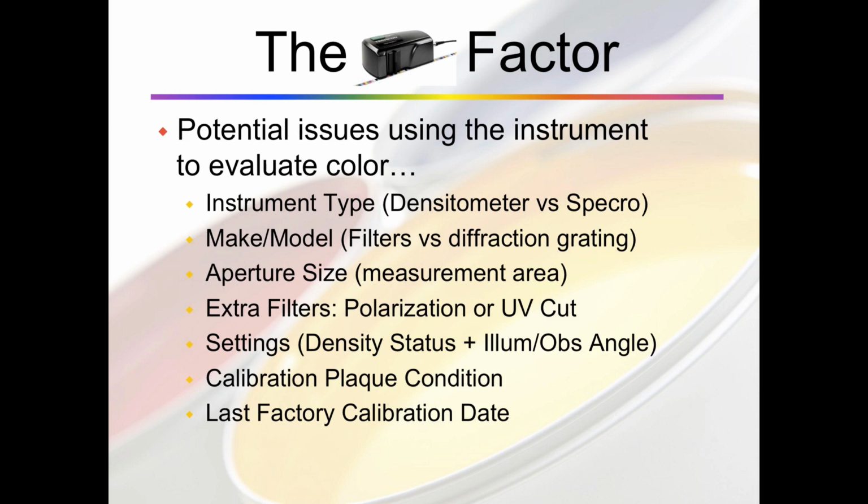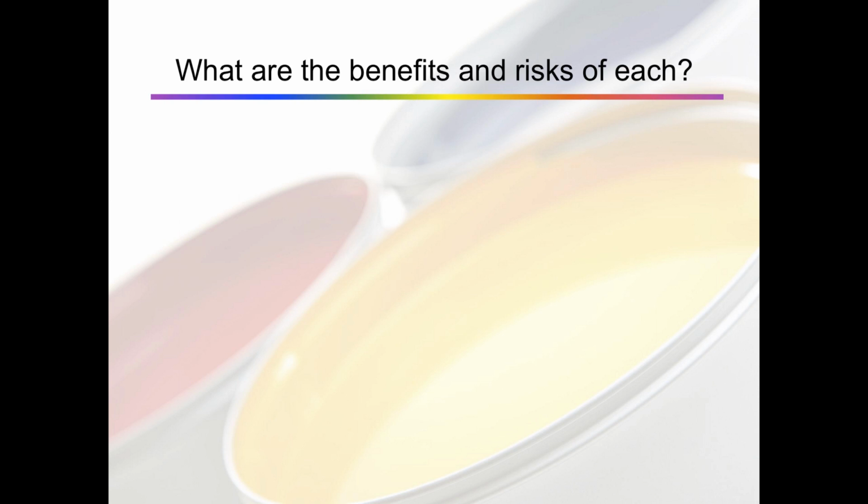So it's important that if you do have to do it every 12 or 24 months, that you're following that procedure and that you're ensuring your device is always certified from the manufacturer, ensuring that as it ages, it's consistently returning the results you expect.